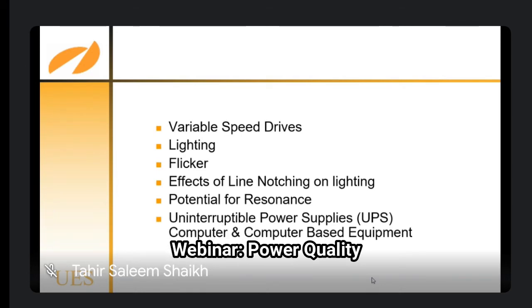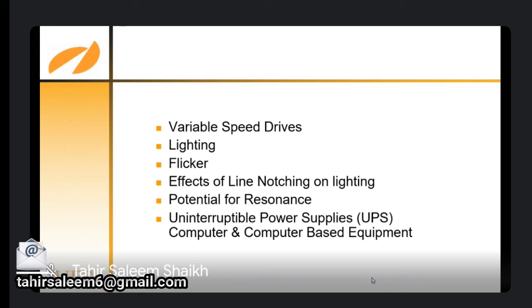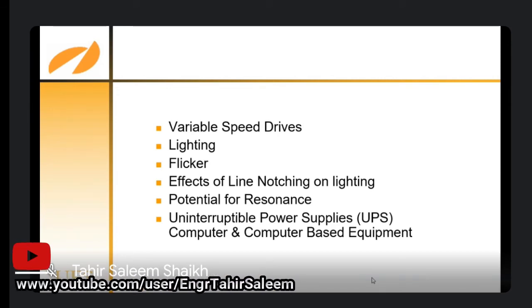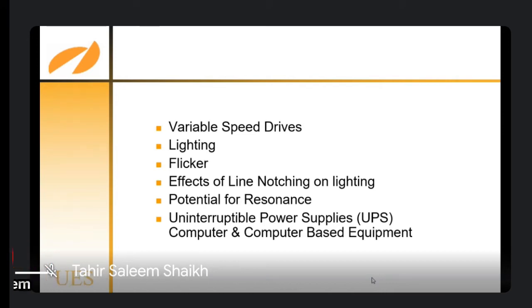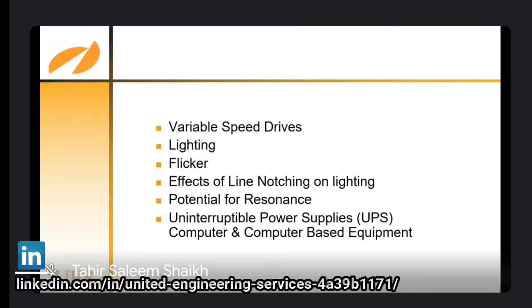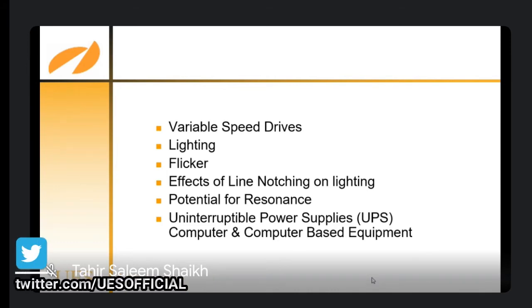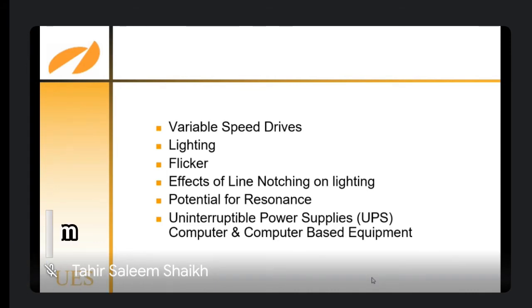Other impacts are on variable speed drives, lighting flicker, effects of line notching on lighting, and potential for resonance. Uninterruptible power supplies may destroy computers and computer-based equipment. I have a lot of examples of harmonics problems. Even in different big hospitals in Karachi, Pakistan, where they created an ultrasound lab, there was a lot of distortion in images because of harmonics. These harmonics were coming from the UPS, and the UPS gives them the third harmonic, and this is very dangerous for them.